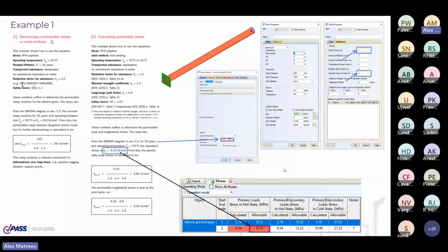We calculated the allowable stresses using the SIGMA engineering guide and created the same model in START-PROF and compared the stresses, so you can see it is the same. And actually in START-PROF it's more accurate than in the SIGMA example, because START-PROF calculated using an equation, but SIGMA engineers just took the stress from the graph.